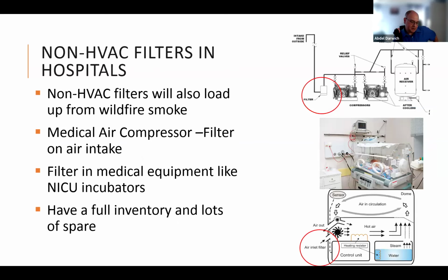Moving on, I've talked a lot about HVAC filters, but during wildfire smoke I got interesting feedback from some hospital owners. It wasn't only the HVAC filter that was loading up — there's also your compressed air. Compressed air is one of the medical gases used in hospitals, usually generated by an air compressor in your mechanical room, and that air compressor sucks air from outside through a filter.